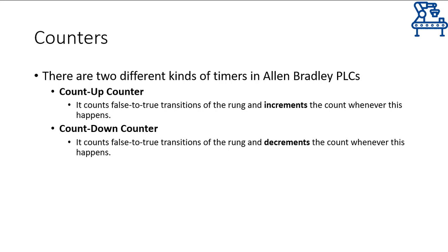We hope that you have understood the working of timers. Now let's talk about counters, which are as important as timers. In Micrologix and SLC PLCs from Allen Bradley, there are two kinds of counters: the count up counter and the count down counter. Both counters count the false to true transitions of the rung conditions.